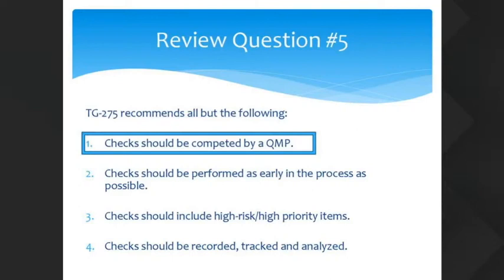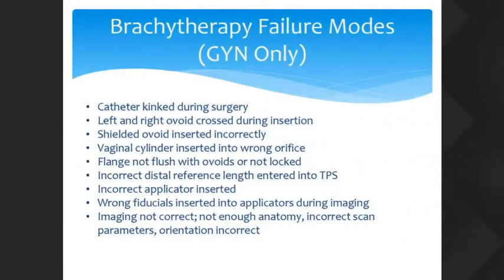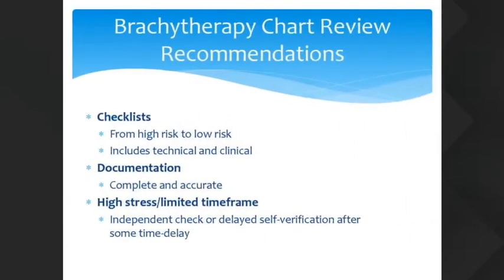All right, in addition to external beam radiation therapy failure modes, TG275 put a small group together to address GYN brachytherapy procedures. We couldn't tackle all brachytherapy procedures, so we decided to narrow down only with GYN. And here are some of the failure modes that were listed. And recommendations for GYN brachytherapy include checklists that were high risk, and they're ranked from high risk to low risk.